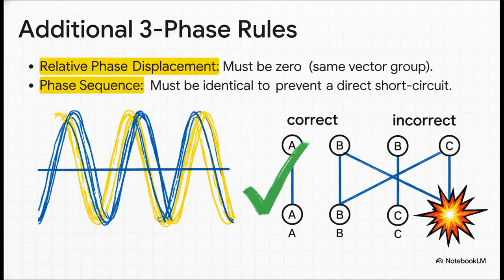First is something called relative phase displacement. Basically, it's got to be zero. This just means the output voltages of the two transformers have to be perfectly in step with each other, with no time lag or angle difference. Engineers call this making sure they're in the same vector group. If you mix and match groups, it just won't work.